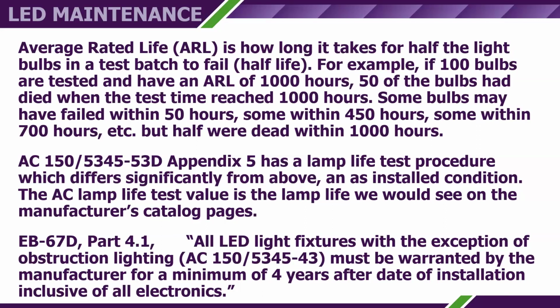Advisory Circular 150/5345-53D, Appendix 5, which is our airport lighting equipment certification program, has a lamp life test procedure which differs significantly from above. It's an as-installed condition. In order to have a lifetime for the light source on the catalog cut sheet, the third-party certifier runs a test that actually duplicates what it would be in service. So it takes the light source, puts it in the fixture, and then evaluates it under actual in-service conditions. And that's the AC lamp life test, the lamp life we would see on the manufacturer's catalog pages. So it's actually a realistic value of the light source.